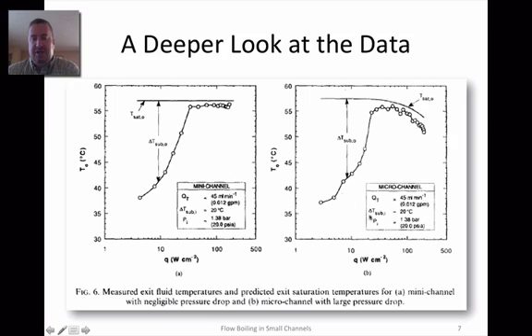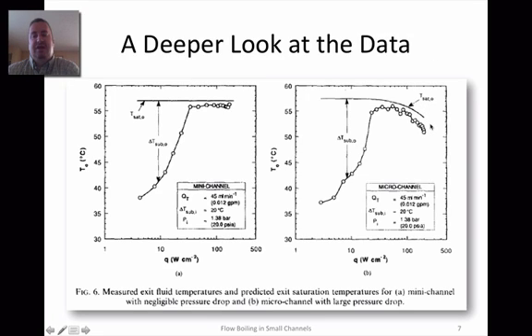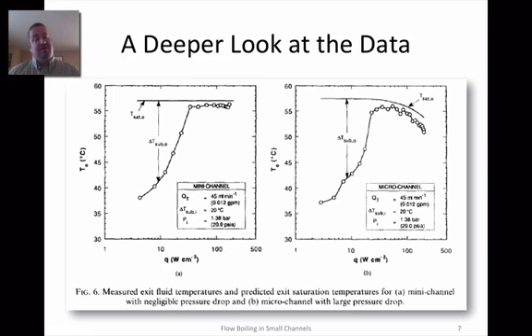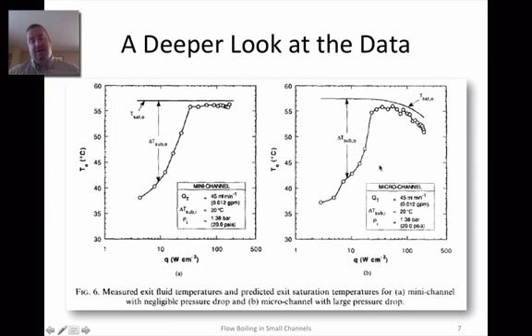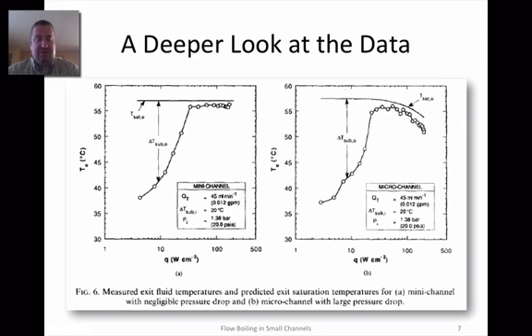Importantly, for the micro channel — which is on the right — because of that large pressure drop, the saturation temperature, which is the boiling temperature, of the outlet condition decreases. If you were really to design a system, you'd have to account for that. That large pressure drop produces a smaller outlet saturation temperature, and that causes the outlet temperature of the fluid to decrease — which overall makes for less favorable overall heat transfer in a system.